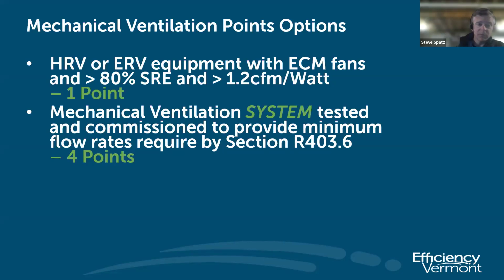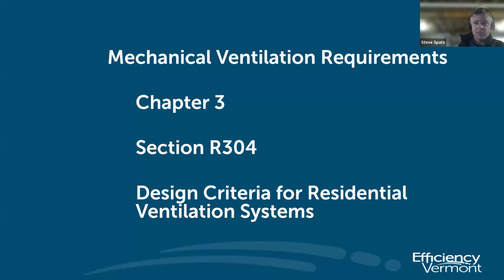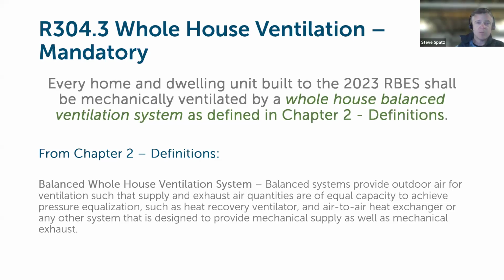And thankfully, in my opinion, the code has caught up to that reality, and now as of July 1st, balanced heat recovery ventilation is mandatory. So there is a minimum performance requirement of a 75% SRE, sensible recovery efficiency, for either an HRV or ERV as your base standard of what to specify and needs to be installed. But you can earn a point by putting in a higher efficiency heat recovery ventilation piece of equipment. And then you can earn 4 points if you're actually testing and commissioning that ventilation system. Why this is important, I'll just get into this in a little bit more detail.